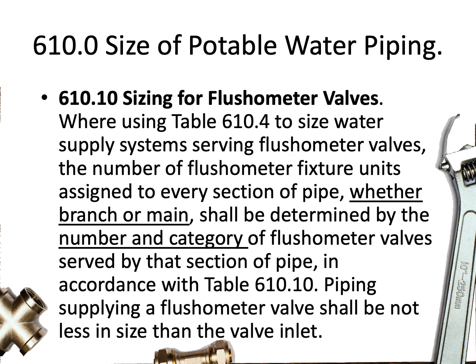Starting in Section 610.10, Sizing for Flushometer Valves. We're using Table 610.4 to size water supply systems serving flushometer valves. The number of flushometer fixture units assigned to every section of pipe, whether branch or main, shall be determined by the number and category of flushometer valves served by that section of pipe, in accordance with Table 610.10. Piping supplying a flushometer valve shall be not less in size than the valve inlet.